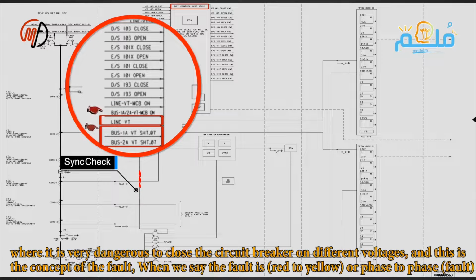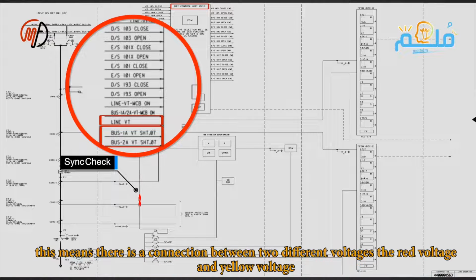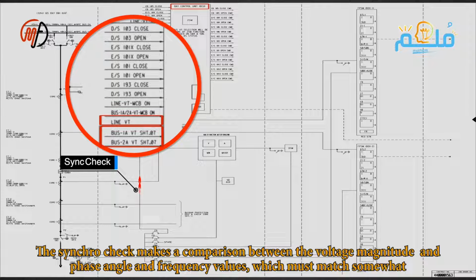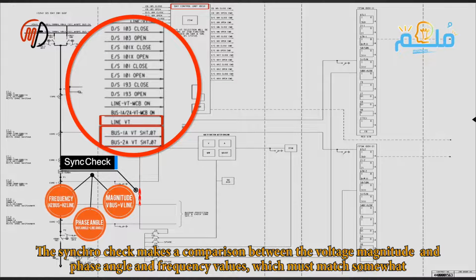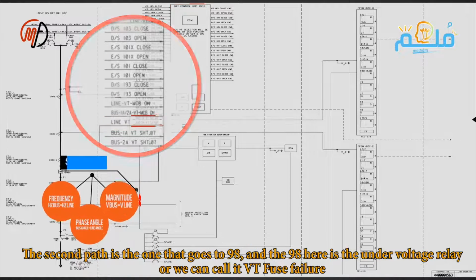It's very dangerous to close the circuit breaker on different voltages. So when we say that the voltage is red to yellow, or phase-to-phase voltage, it means there's a connection between two different voltages, the red voltage and the yellow voltage. The synchro check compares the magnitude values, phase angle, and frequency, which should somewhat match.